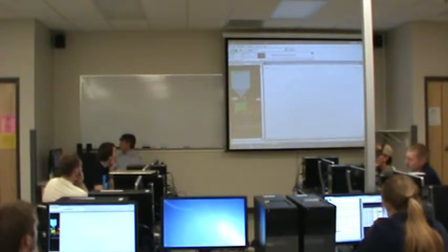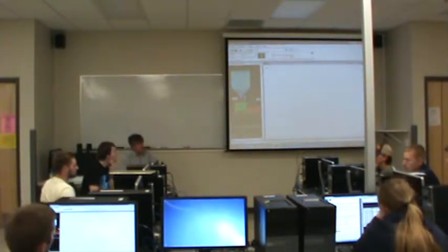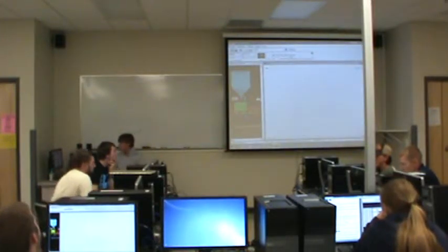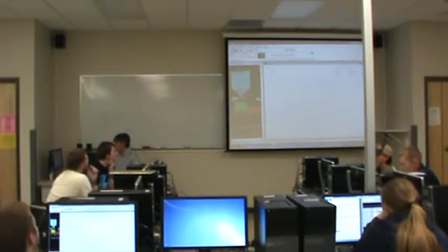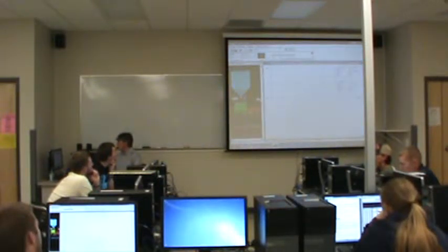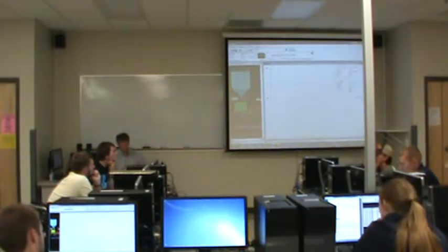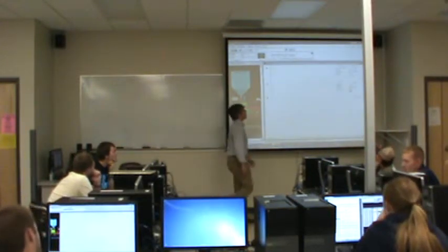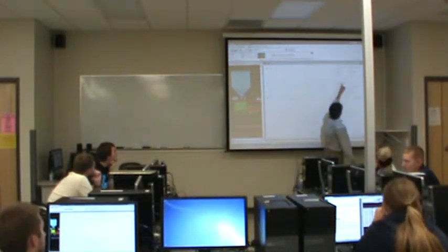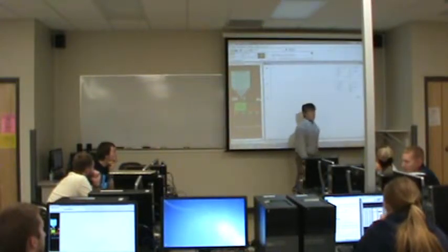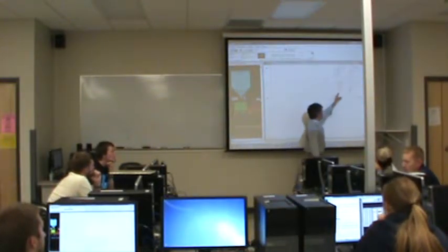Let's see. So timers and counters are in the same tab because they're very similar instructions. In fact, if I pull down a timer on instruction and a count up CTU instruction, they look a lot alike. You have to give both an address. You have to give both a preset and an accumulation value. And the only thing that's really different is that the timer counts up time, in tenths of a second, so 0.1. So we get to choose the time base. Whereas the counter just counts events.